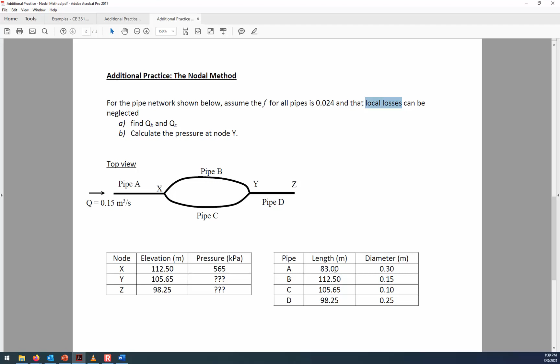Remember, the nodal method allows us to figure out the distribution of flow when it branches at a node. Here we know the flow through pipe A is 0.15 cubic meters per second, and then it branches - some goes through pipe B, some through pipe C. To simplify, you can assume the F value so you don't have to calculate it, and local losses can be neglected. But for each pipe you do have its length and diameter.